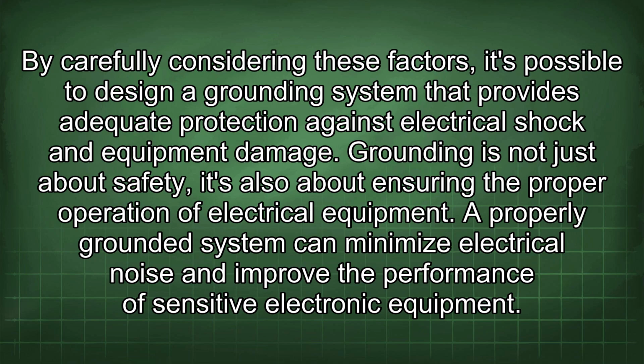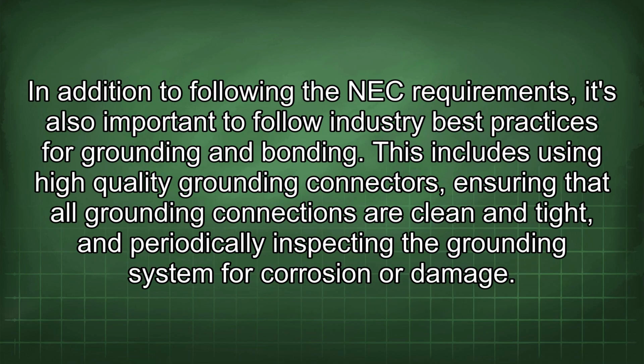Grounding is not just about safety, it's also about ensuring the proper operation of electrical equipment. A properly grounded system can minimize electrical noise and improve the performance of sensitive electronic equipment. In addition to following the NEC requirements, it's also important to follow industry best practices for grounding and bonding. This includes using high-quality grounding connectors, ensuring that all grounding connections are clean and tight, and periodically inspecting the grounding system for corrosion or damage.